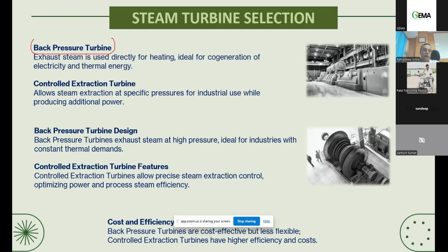In the back pressure turbine, steam is given to the turbine, and it is extracted. The main steam comes to the turbine, and the process steam is taken and goes to the process. If temperature control is needed, you may put a desuperheater here. So this is a simple back pressure turbine. In a back pressure turbine, obviously the exhaust steam is at high pressure, which is ideal for your process.